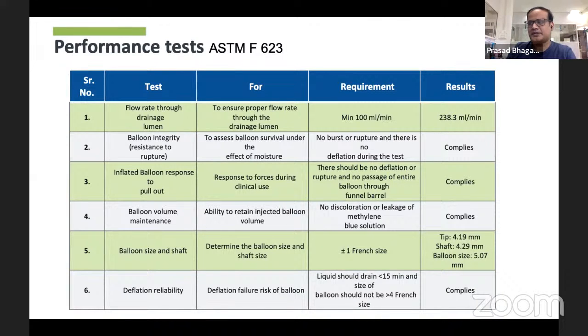Because sometimes, if the patient just gives a jerk to the catheter, or his urine bag gets stuck somewhere and that creates a jerk, the balloon might rupture or the catheter might slip out. So to avoid this, we also check how the balloon responds to the pull out, that is, the clinical forces being used. The requirement is that there should be no deflation or rupture and no passage of the entire balloon through the funnel barrel. Now this is an experimental setup.